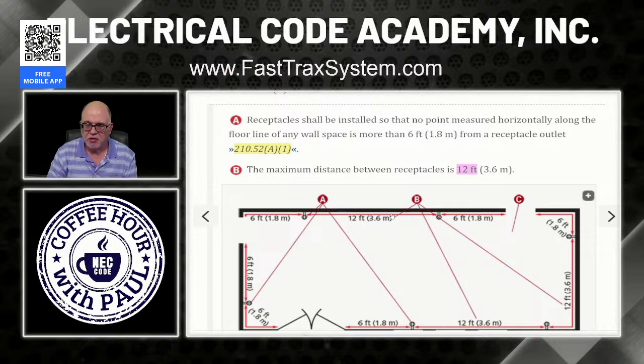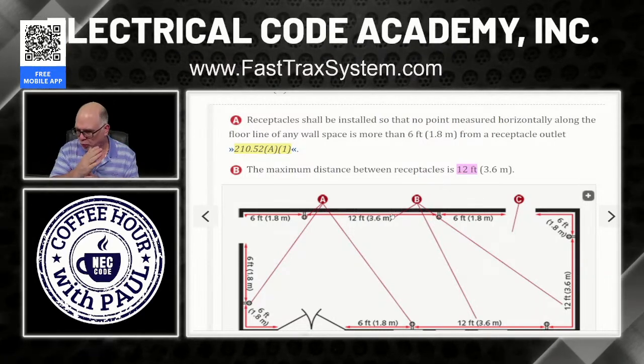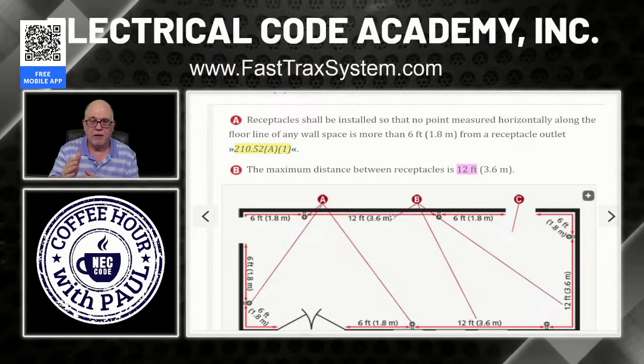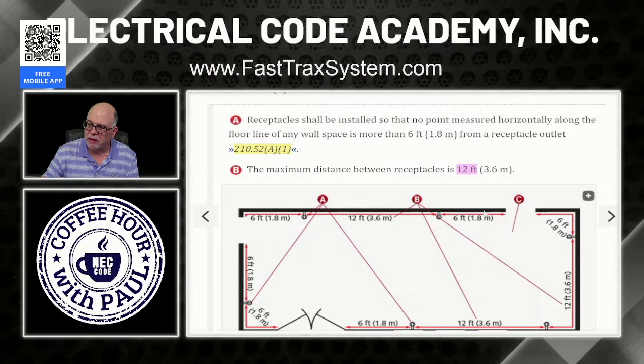So that's where you hear us talk about this old saying, 6 foot, 12 foot rule. That's what it means. 6 feet from a break in the floor line, and then the distance between receptacles could go up to 12 feet, so that at no point along the wall line am I more than 6 feet from a receptacle, okay? Now, you notice here is another break in the wall line. Then this receptacle is 12 feet from this one, but it has to be within 6 feet from this one.